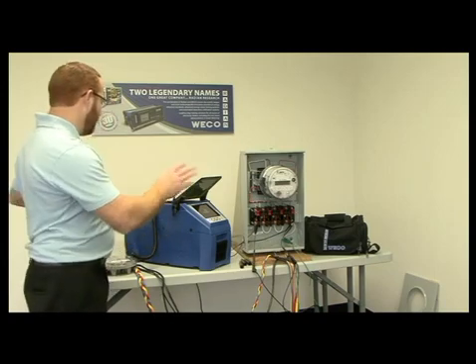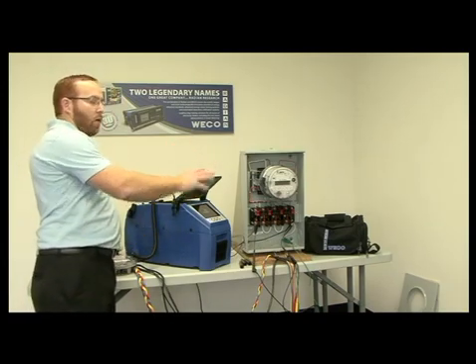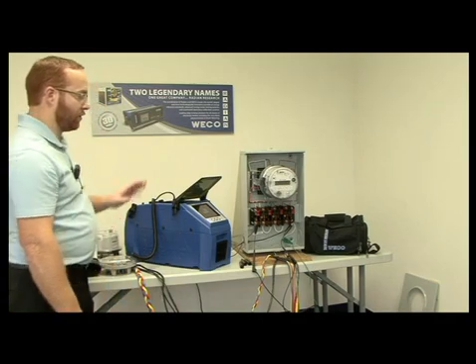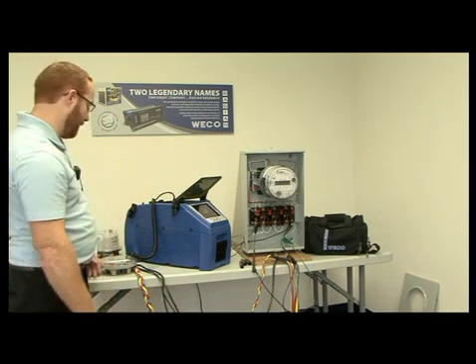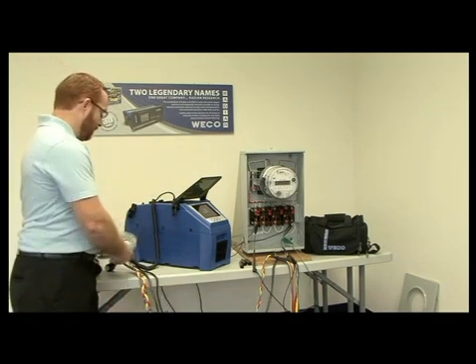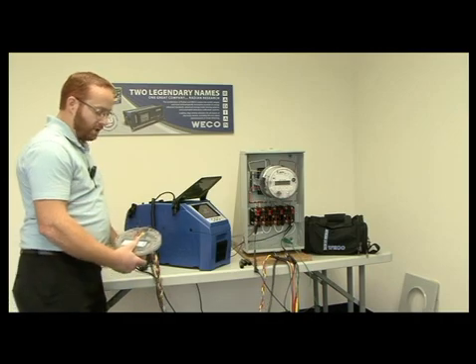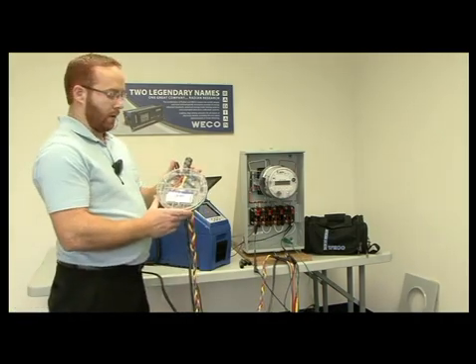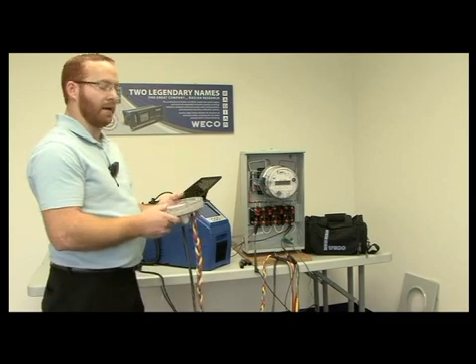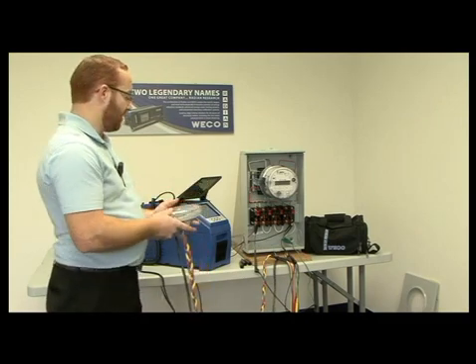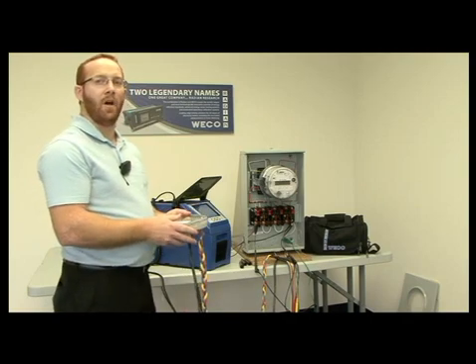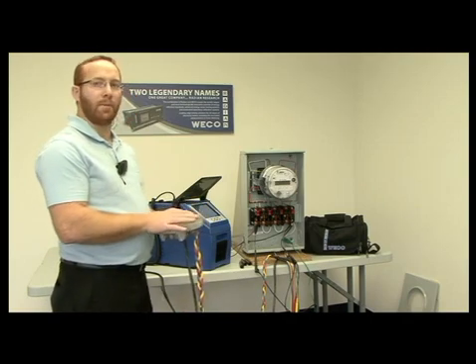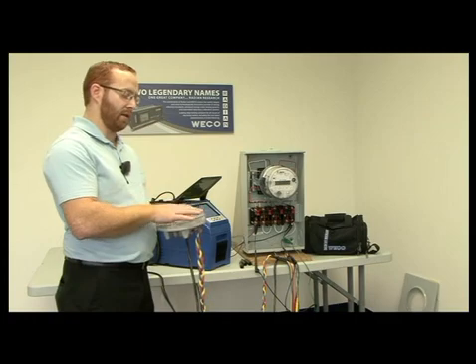So today we're going to be testing the meter while it remains installed in the test switch interface of a transformer rated meter. And we're going to be using the RB-MTA meter test adapter. This meter test adapter is configured in a form 9 connection scheme, but the software will allow me to test all of the transformer rated meters via this configuration.